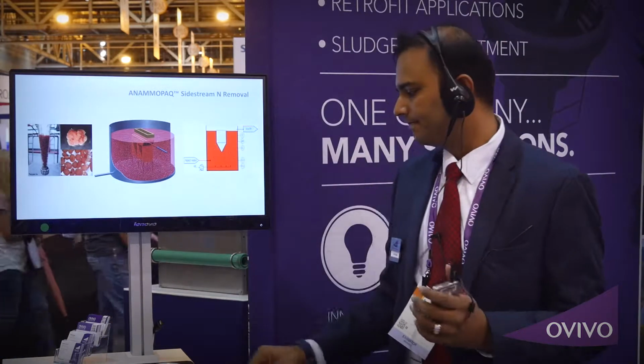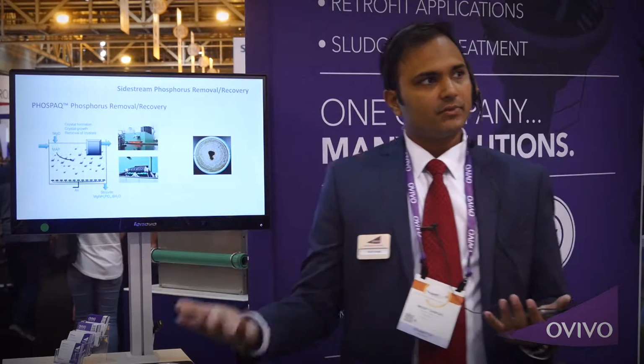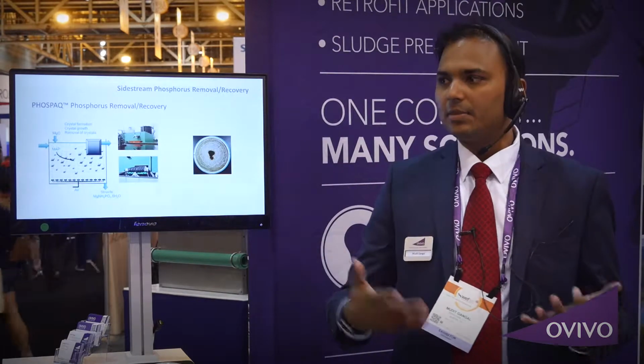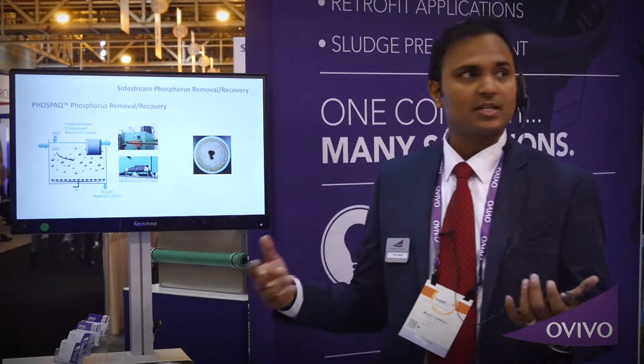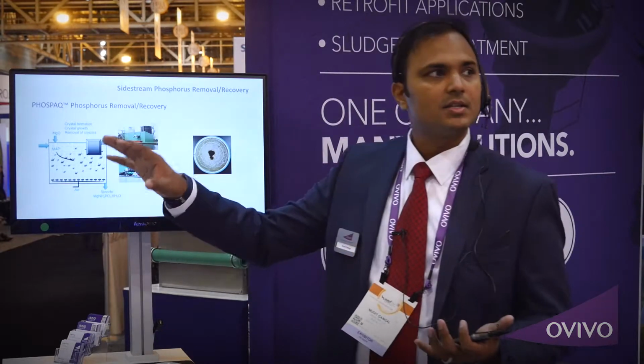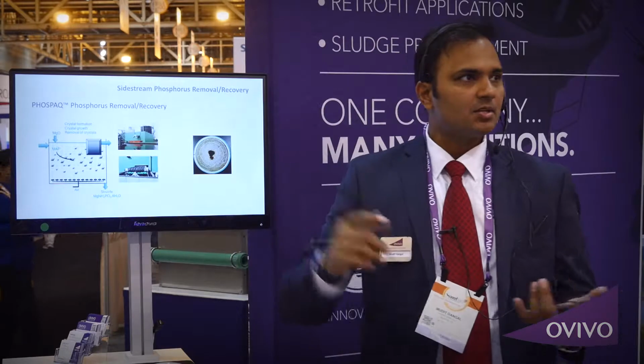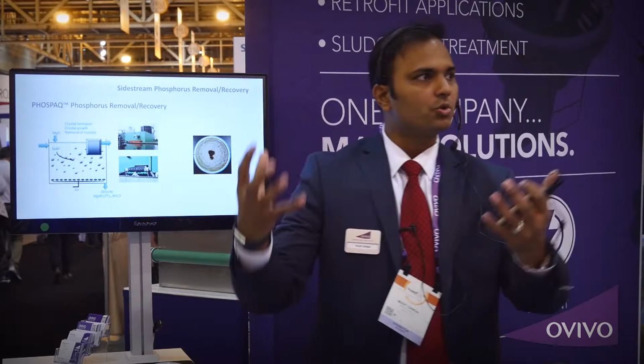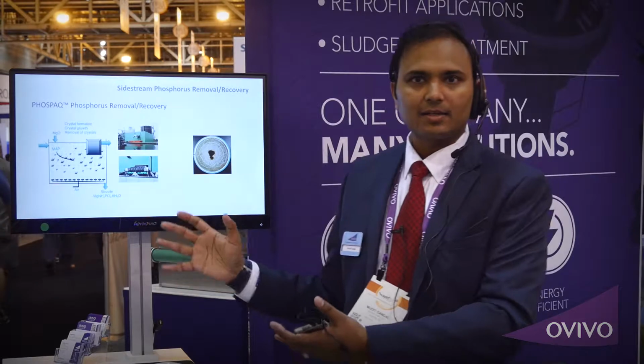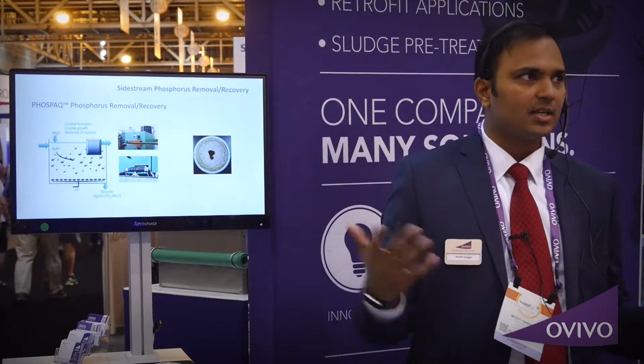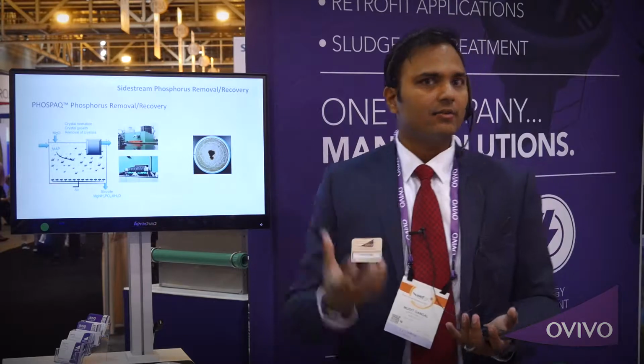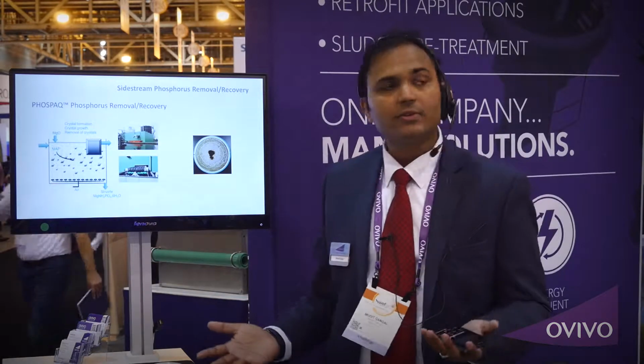A very simple process. A similar thing that could be done is phosphorus, where on the side stream, the dewatered centrate that's produced or filtrate, scaling can be an issue at facilities because of the struvite that's produced, especially with BioP at the plant. And what you're trying to do is you aerate the side stream to strip out carbon dioxide. You add magnesium, and there's ammonia and phosphorus already in the influent. So you form magnesium ammonium phosphate or struvite. So you have controlled struvite precipitation inside the reactor rather than that scaling happening inside your pipes and other areas. So as a result, you're able to reduce the O&M cost at your plant, and if needed, you could recover the struvite as a valuable product. You could sell it, make money off of it as a fertilizer.